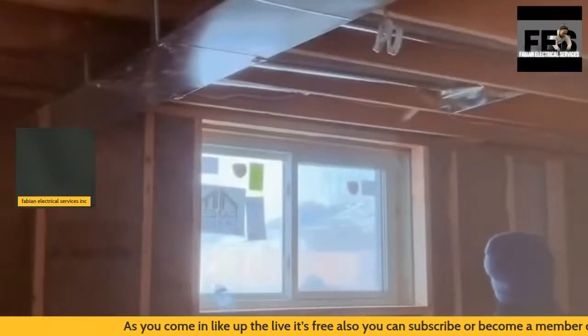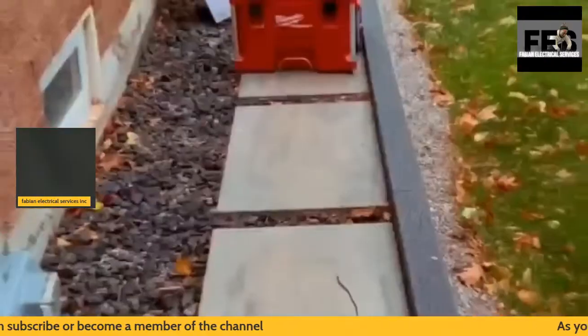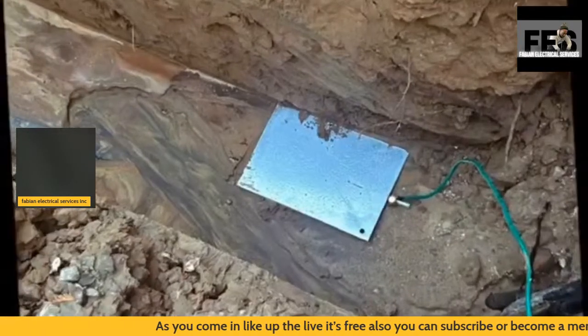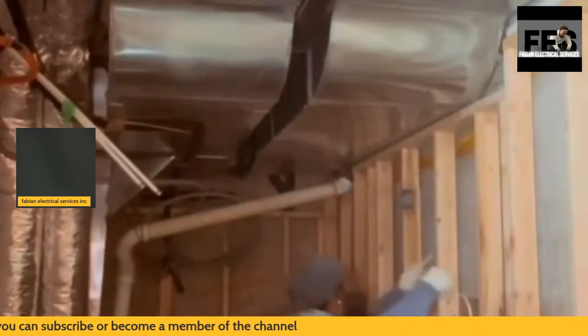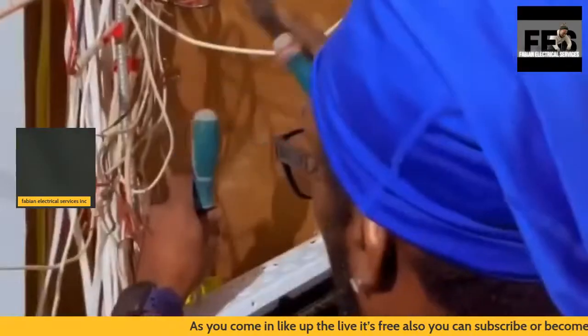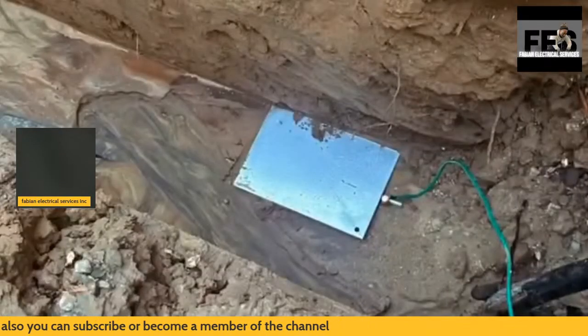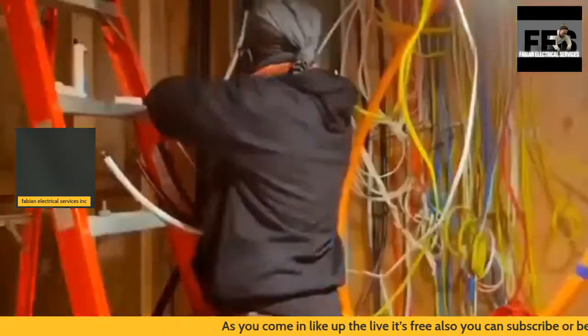What you had there in that installation was basically a 400 amp electrical disconnect installation. You'll see the 250 kcmil wire installation that's already in place. There are many other videos where you'll see me installing the actual cable. I've already played my AC disconnect video, and that's one part of the installation for the 400 amp disconnect. I'm going to run another video, same style disconnect.